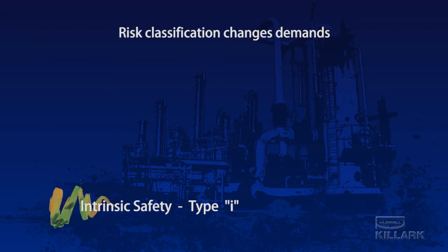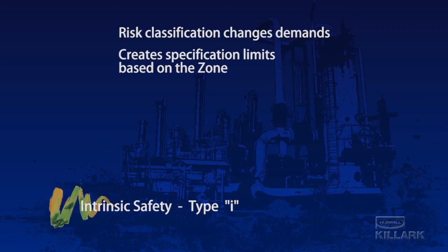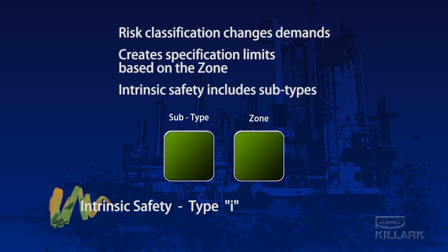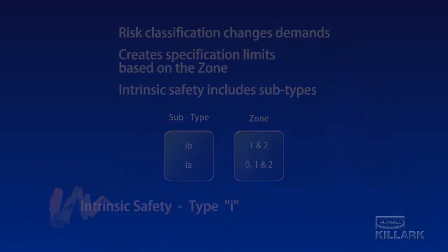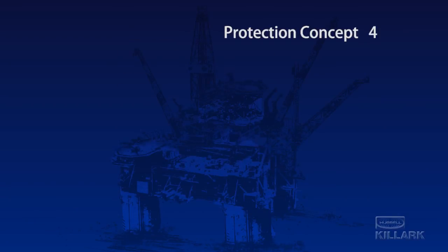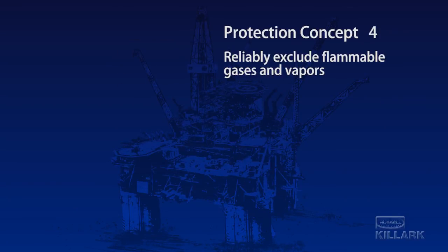Each risk classification places different demands on the equipment and confines certain technologies to particular zones. In the case of intrinsic safety, there are subtypes that have been targeted toward the particular risk. Type IB is intended for use in Zone 1 and 2 applications. Type IA is permitted for use in Zone 0, in addition to Zones 1 and 2. The final concept employs designs and procedures intended to prevent the flammable gases or vapors from coming in contact with a potential source of ignition.